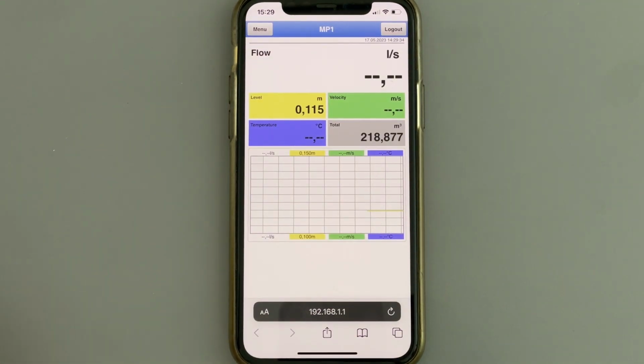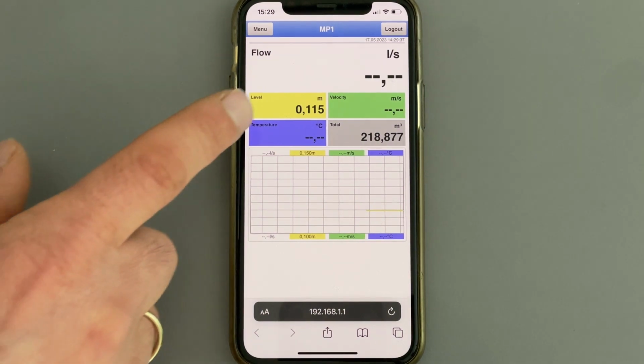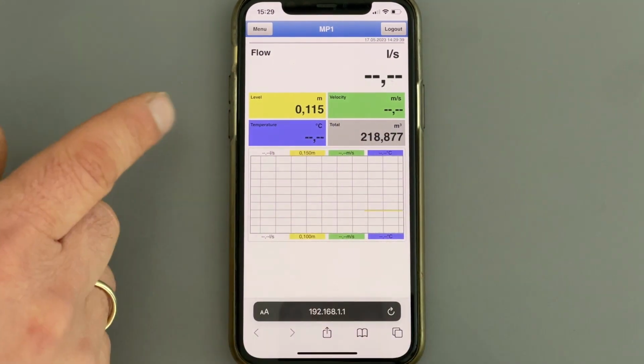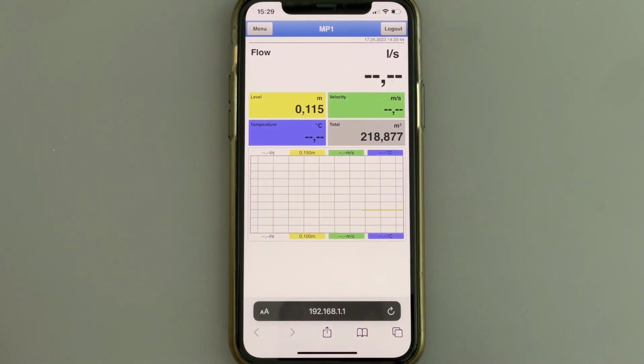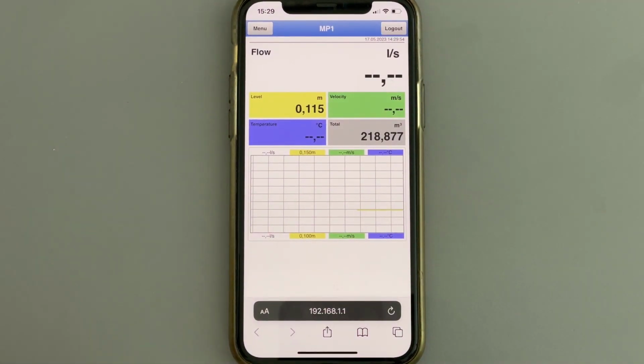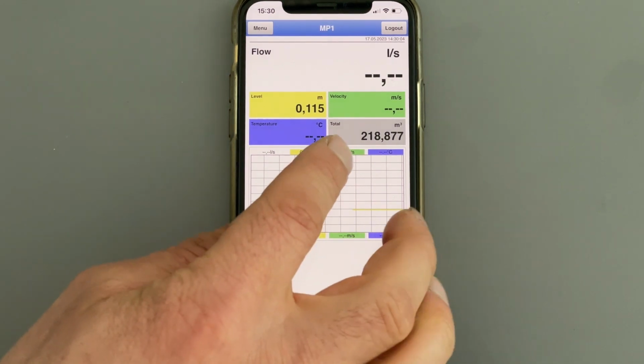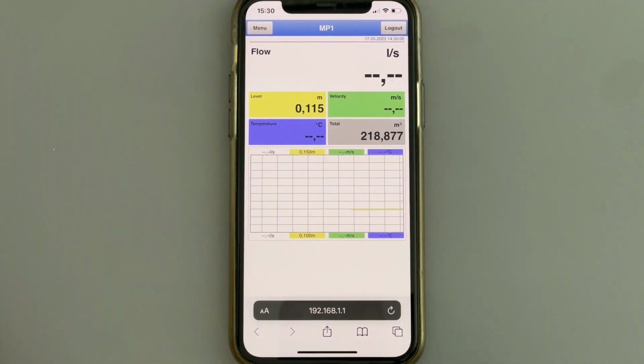And after you have established the connection, you will see here in the main screen the flow. At the moment, the sensors are not attached to a pipeline, therefore the dashes. I have the level, which in this case shows the pipe diameter, the velocity of the flow in the pipe, the temperature, which is not a measured temperature but a calculated one, and the totalizer of the volume of water which flows through already.